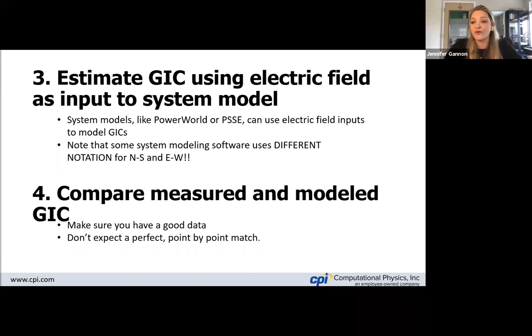Here's an example from that EPRI report that I mentioned. We consider this a decent match. This is measured and modeled GIC in a system. This is published in this report. You can see how we got to this tiny little event here, but this is considered a good match because the modeled GIC at the peak is pretty close to the measured GIC at the peak. This was because we had really good magnetic field data from the Fredericksburg Observatory. We had some good ground models and a very good system model, and we were able to reproduce these.